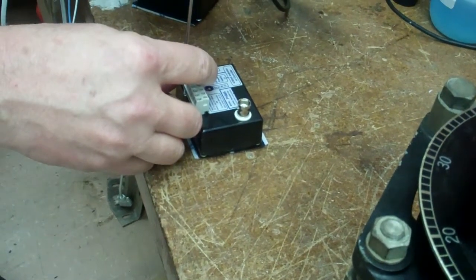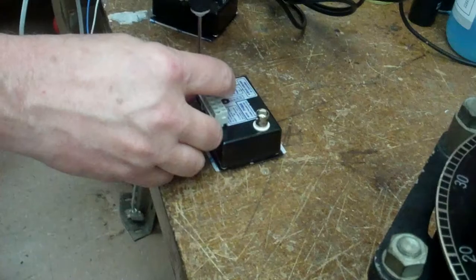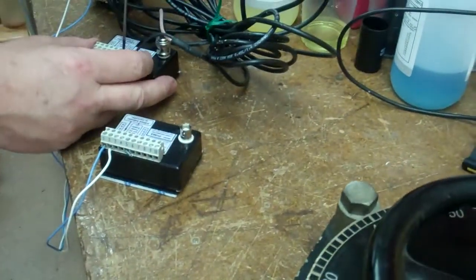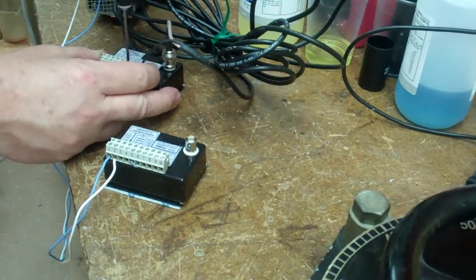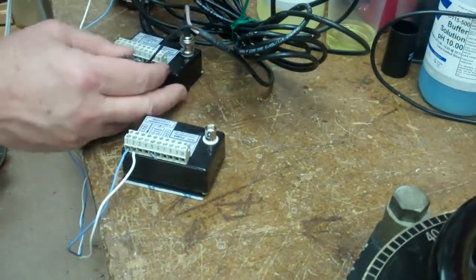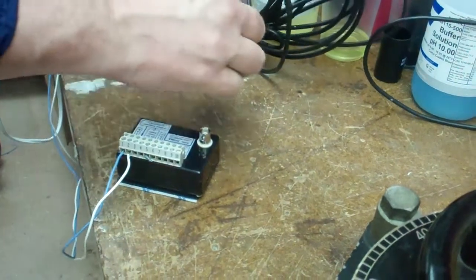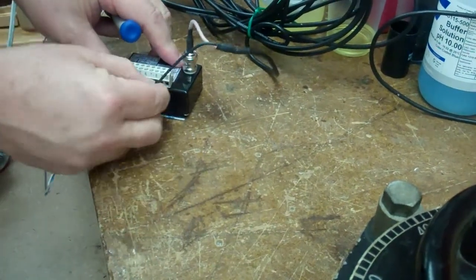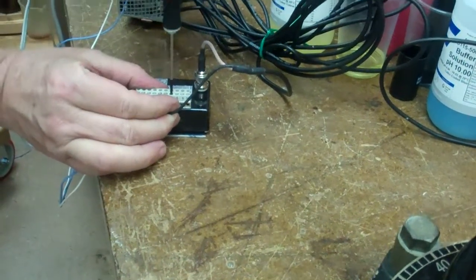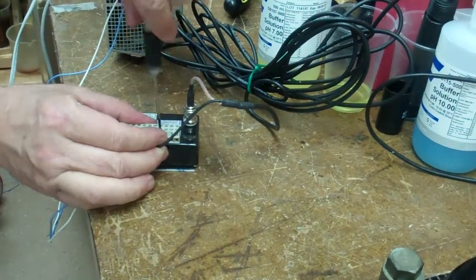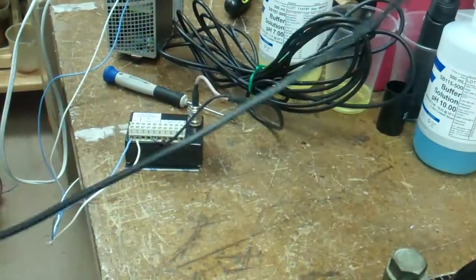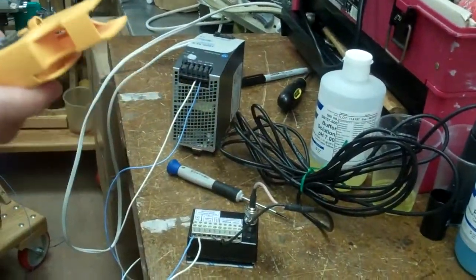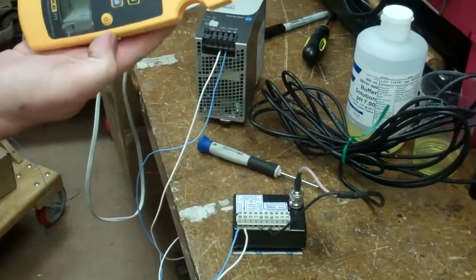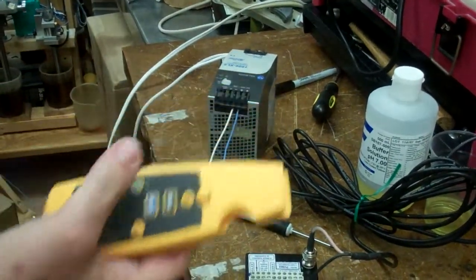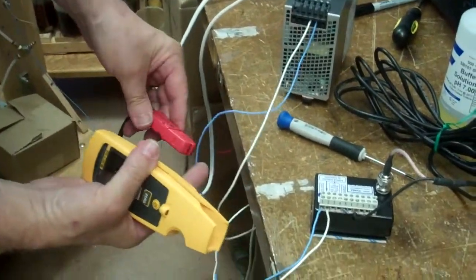Okay, I'm connecting up my DC power. This is a milliamp current loop transmitter. I have a pH probe here, which is currently sitting in a buffer solution of 10. Unplug that. Plug it in. Put back on the ground pin. We take our milliammeter, which I'll just turn on. I can 0 it. Attach this to the blue wire, which is the current flow.